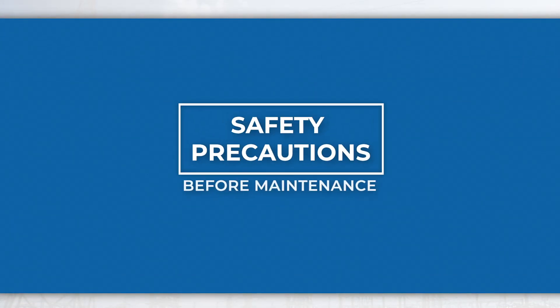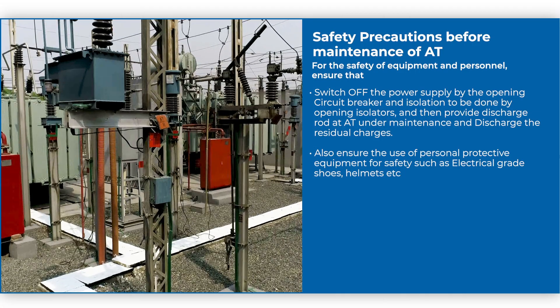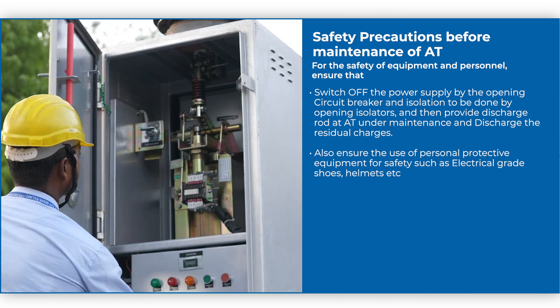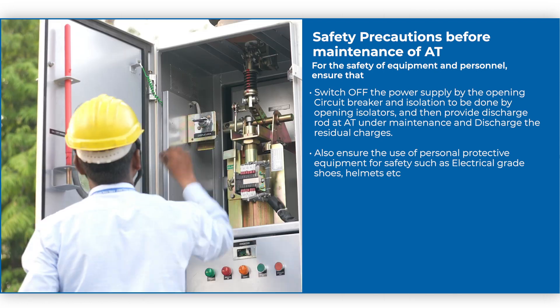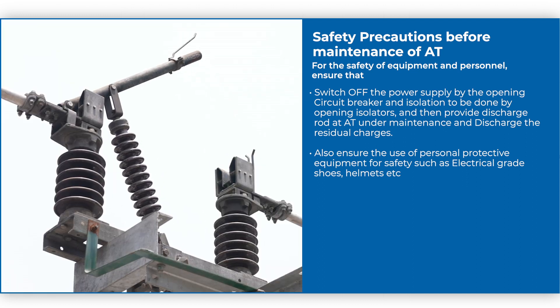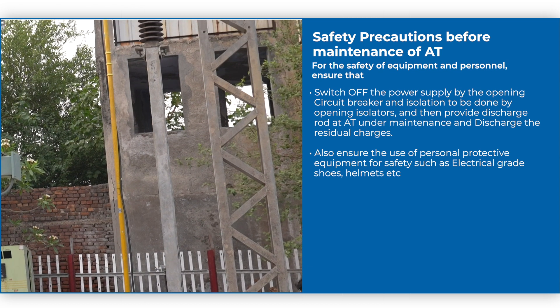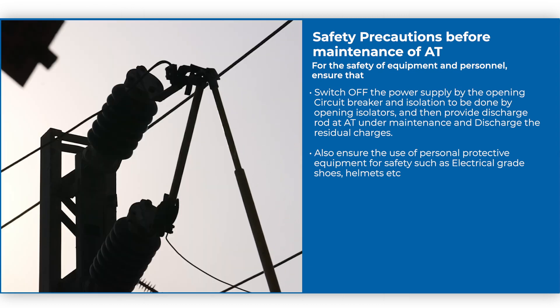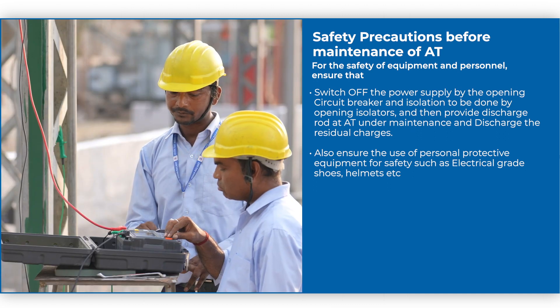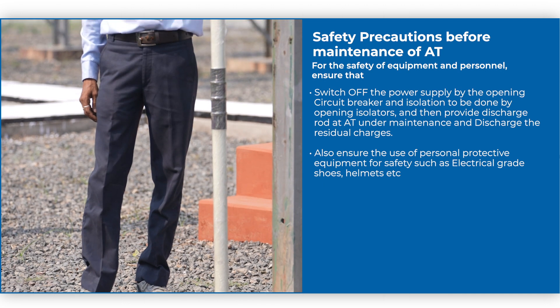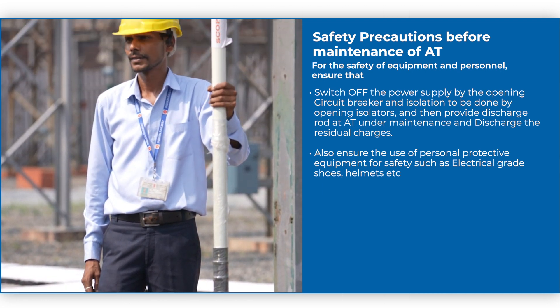For the safety of equipment and personnel, ensure that the power supply is switched off by opening the circuit breaker, isolation to be done by opening isolators, then provide a discharge rod at the equipment under maintenance and discharge the residual charges. Also ensure the use of personal protective equipment such as electrical grade shoes, helmets, etc.